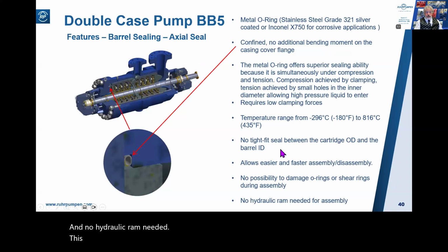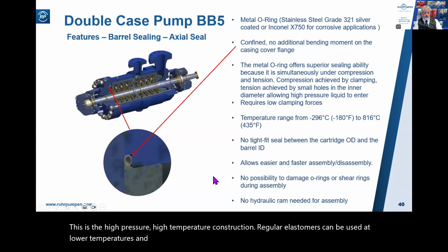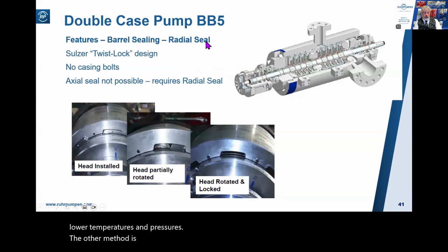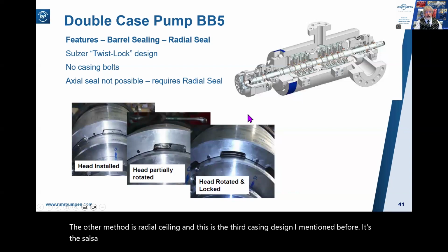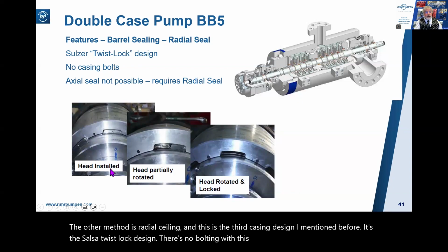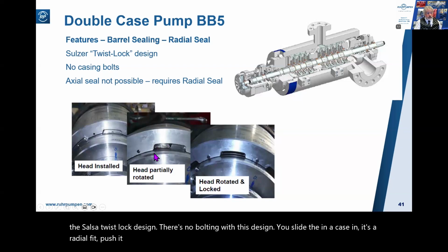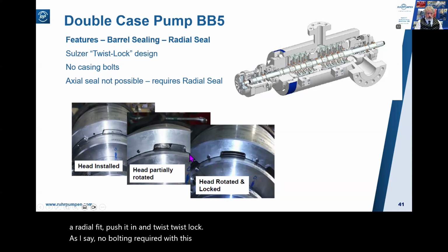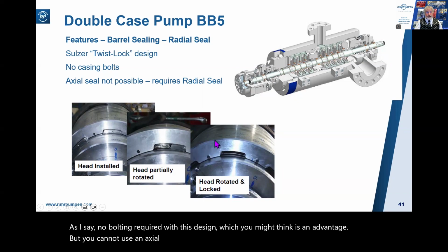This is the high pressure, high temperature construction. Regular elastomers can be used at lower temperatures and pressures. The other method is radial sealing. And this is the third casing design I mentioned before. It's the Sulzer twist lock design. There's no bolting with this design. You slide the inner case in, it's a radial fit, push it in and twist lock. As I say, no bolting required with this design, which you might think is an advantage, but you cannot use an axial seal, which requires compression from the bolting. Instead, it uses a radial seal.